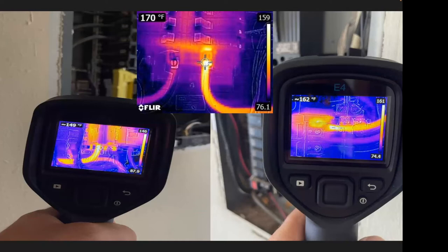Well, what did they set? Great question. Ambient, whatever ambient is for the day. Right here, ambient is 74, which means the lowest temperature I'm recording is about 74. That number plus 50 is allowable per the electrical guidelines. If it's 20 degrees outside, you can't expect the panel to be very hot. If the breaker is overdoing it with power, there's too much resistivity inside the breaker. So it's 50 over ambient. In this case, these are almost 100 over, maybe 80 over is the lowest one. They're unseen except with specialized equipment. That's why I like to show them, because these cameras are expensive, they do their job, and they're worth their weight in gold.